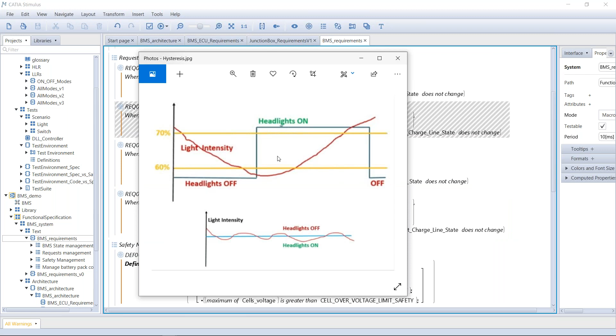The example we're going to use is automatic headlights of your car. And what you want, obviously, is when the light intensity is low, you want to switch on the headlights. If you have one limit, it's not going to work properly, you know that. And so in embedded systems, people define hysteresis on tons of topics. Here we're going to say when the light intensity goes under 60% for 2 seconds, switch on the headlights. And wait until we are above 70% for the light intensity for 3 seconds to switch off.